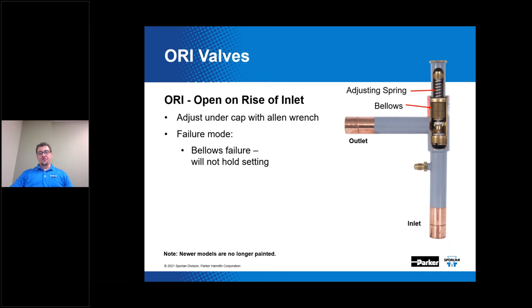Depending on the refrigerant and application, you don't want to use the ORI for R410A refrigerant because it doesn't have a high enough maximum operating pressure. For R410A, we recommend our LAC-HP valve specifically intended for that application. Regarding installation: because the bellows is a flexible seal and responsive, it is susceptible to failure due to overheating. Make sure you don't overheat this valve when soldering it into the system, because a leaky bellows can impact the valve setting and can go unnoticed for extended periods of time.